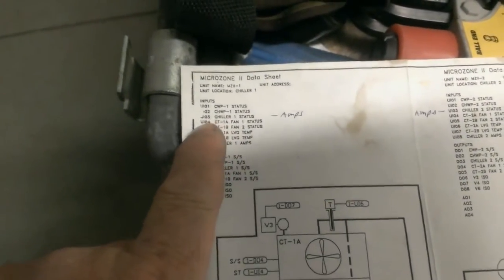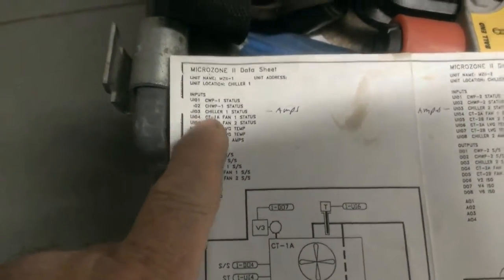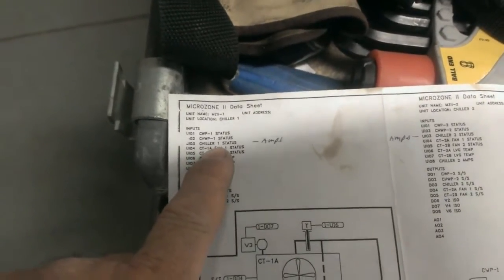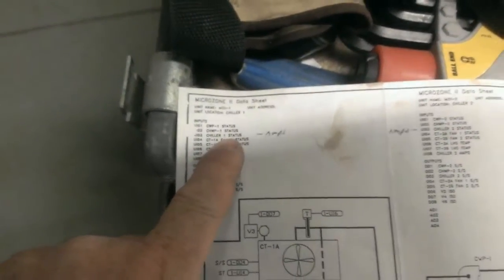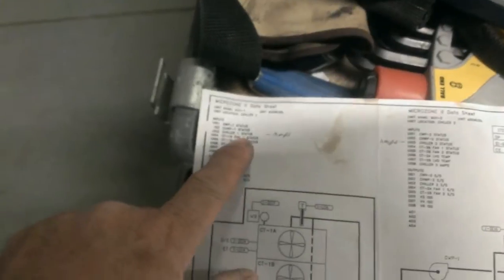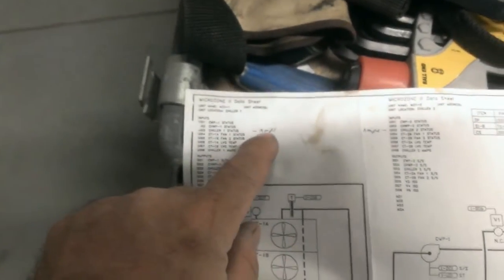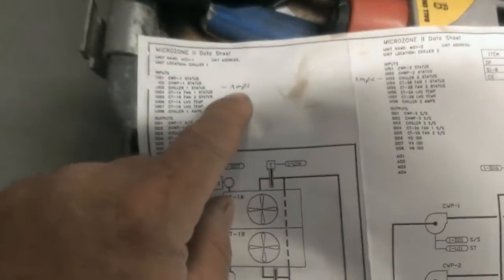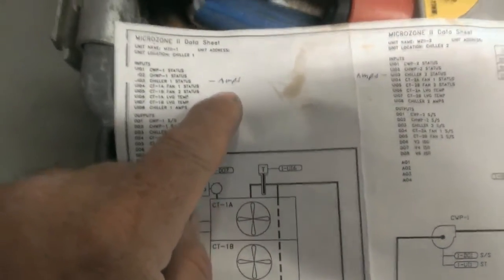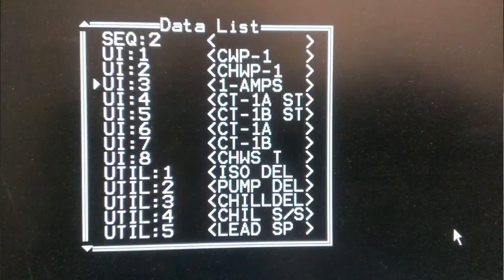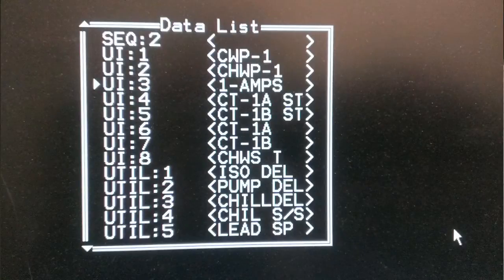The carrier people. But anyway, it would be nice if this EMS schematic was correct. Universal input number three to the EMS microcontroller. Here it said chiller one status and that's what the wire was looking for. But really that's supposed to be amps, which I confirmed when I was into the actual software for the EMS. The DOS based software. Microzone 2 system.